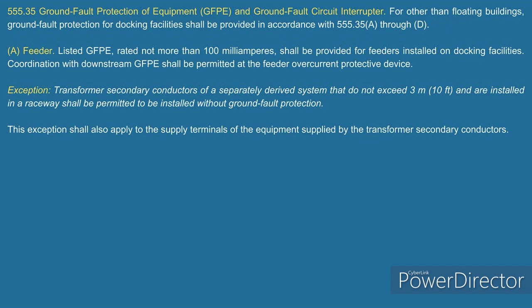So if you look at (A) is where we deal with a feeder, and it says listed ground fault protection of equipment rated not more than 100 milliamperes shall be provided for feeders installed on docking facilities. Coordination with downstream GFPE shall be permitted at the feeder overcurrent protection device. Now, first of all, unlike what he said before, he says a feeder, like if I was going over and hitting a fusible type disconnect, and then I go to a single motor, he says that's a feeder. That's not correct either. I've already showed that.